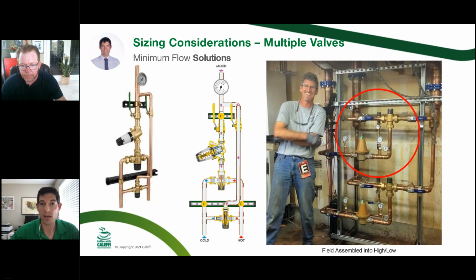The picture on the right was one that was field installed before we had PRVs in the North American market, so you can see behind the pipe there's a small mixing valve and then a bigger mixing valve in the front, and they have two stations. So in that case, you may have struggled to find a single mixing valve to cover all of those different things. So maybe you're going down to that 2 GPM, but you might need to go up to 50, 60. It can be hard to do that with a single thermostatic, which is why high-low stations are popular and have been a good way to go for a long time.